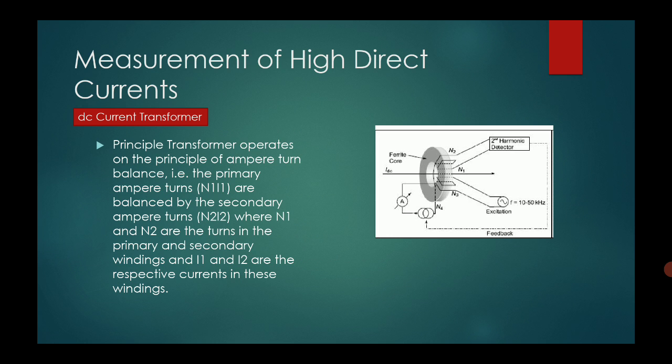We can also measure high direct current using DC current transformers. The schematic diagram is shown here. The transformer operates on the principle of ampere-turn balance: the primary ampere-turns N1·I1 are balanced by the secondary ampere-turns N2·I2, where N1 and N2 are the turns in the primary and secondary windings, and I1 and I2 are the respective currents. When high direct current passes through the ferrite core, it produces a circular magnetic field crossing both N1 and N2 turns, and from the balance value we can measure the high direct current.